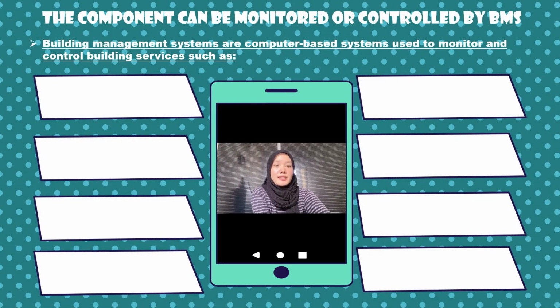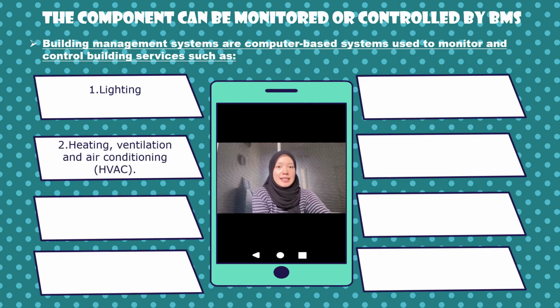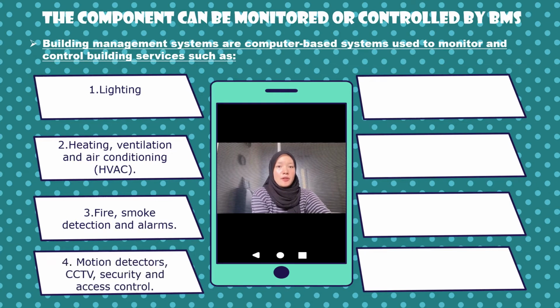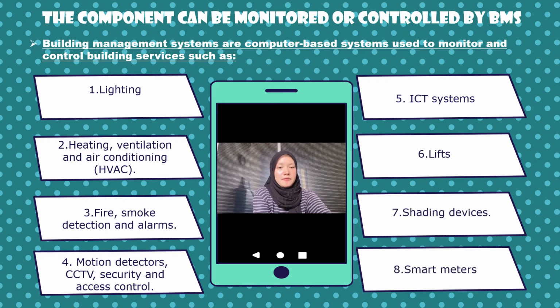This is the component that can be monitored or controlled by BMS. Building management systems are computer-based systems used to monitor and control building services such as: first, lighting; second, heating, ventilation, air conditioning; third, fire, smoke detection, and alarm; fourth, motion detectors, CCTV, security, and access control. Next is ICT system, then lift, shading devices, and smart meters.